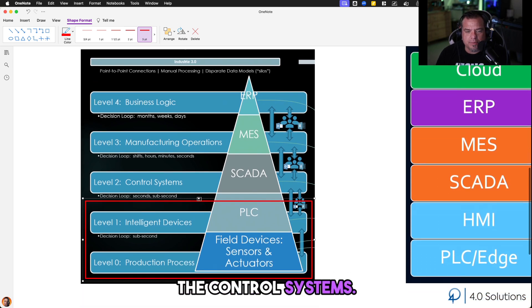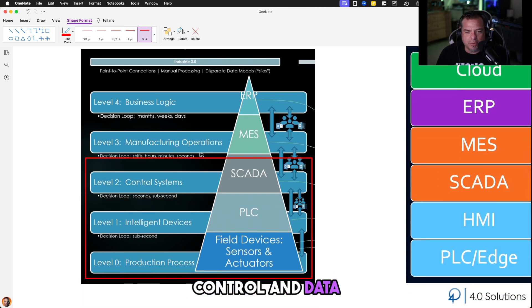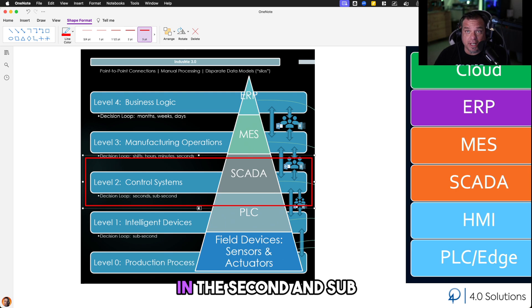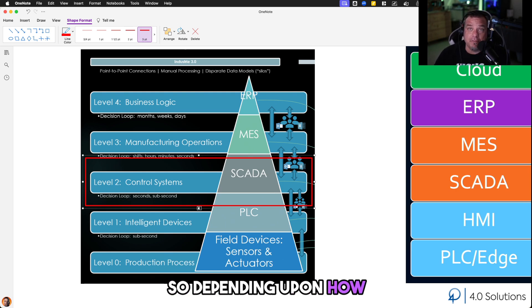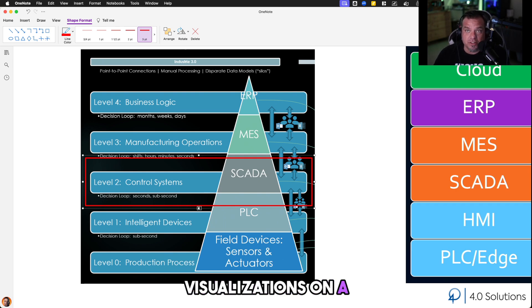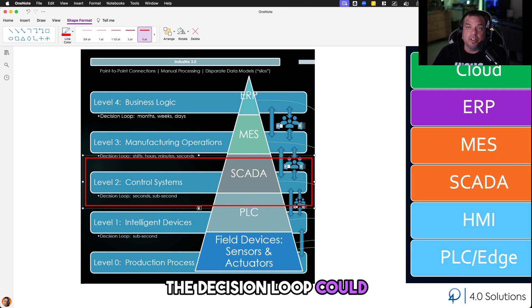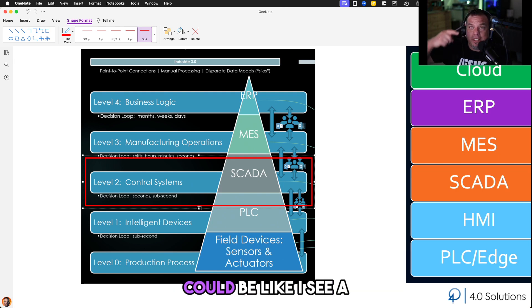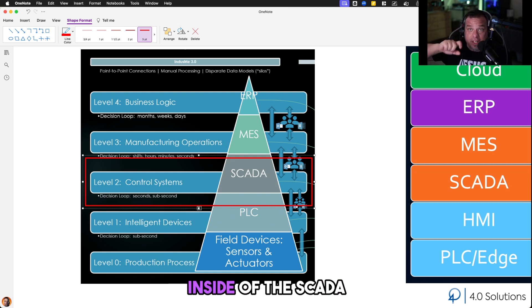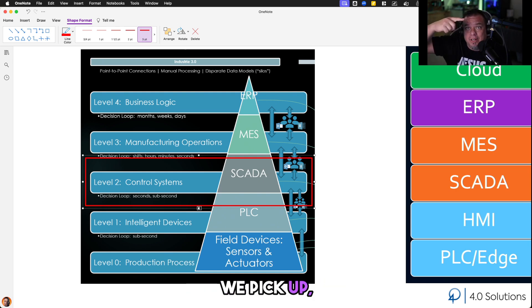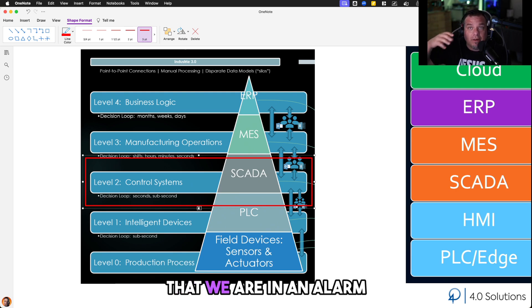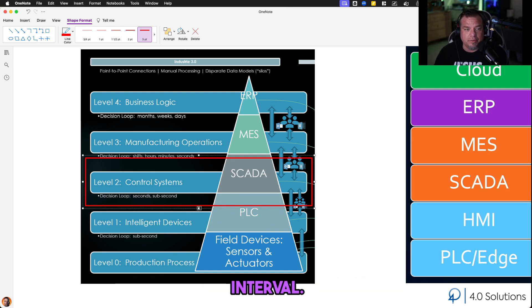We have PID loops that are analyzing data and reacting to that data in sub-second intervals. The control systems — the supervisory control and data acquisition system, SCADA — sit directly above the edge layer. Those decision loops are in the second and sub-second range, depending on how fast your SCADA system can react to data changes and draw visualizations on screen. For example, detecting a high inrush current on a motor contactor closing — managing alarms inside the SCADA system — and within a sub-second, indicating on screen that we are in an alarm state.